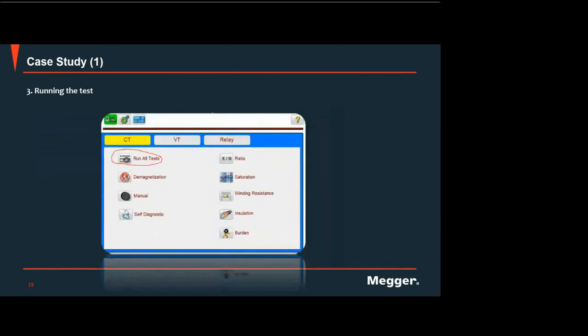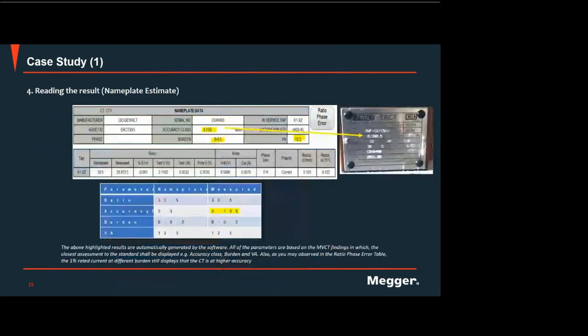All right. Then the good thing with the MVCT is that we can run all tests. Meaning it will do the mag, saturation, ratio, and winding resistance tests in just one go, with just one play button. Now we got the result here. The MVCT finds that the CT is maybe 0.15s because it passed the 0.15s values based on the result. But as you can see here, the nameplate says 0.3, so this is not just 0.3. According to the MVCT, the CT is around 0.15s because of this result, maybe because of this error. So we are not sure yet if the CT is an ERCT because we don't have the value for the 1%.